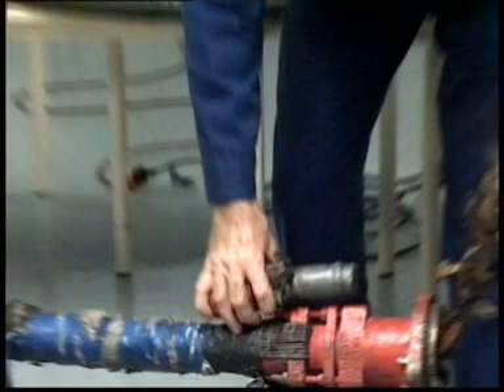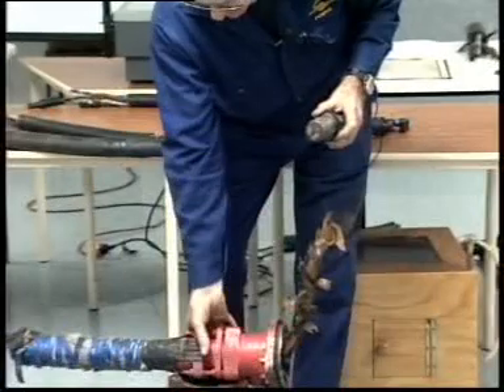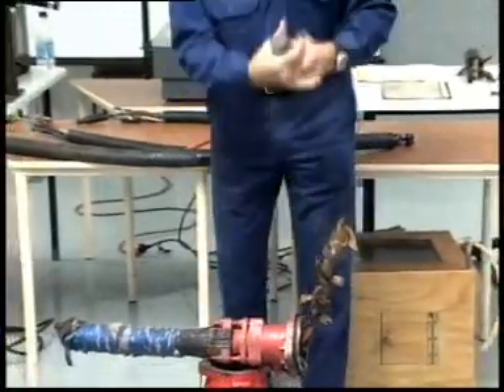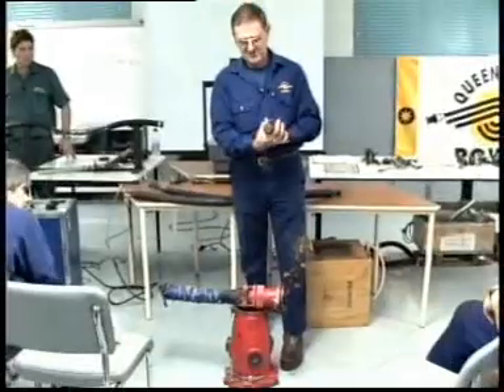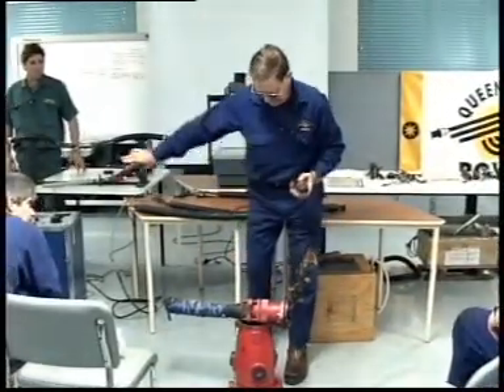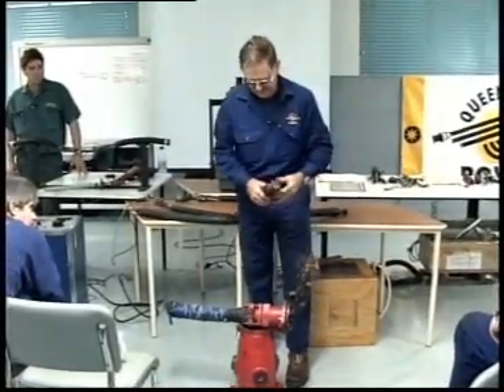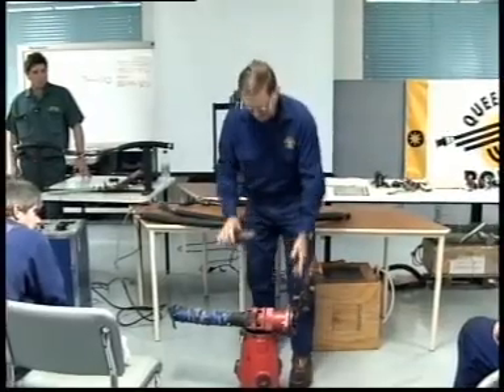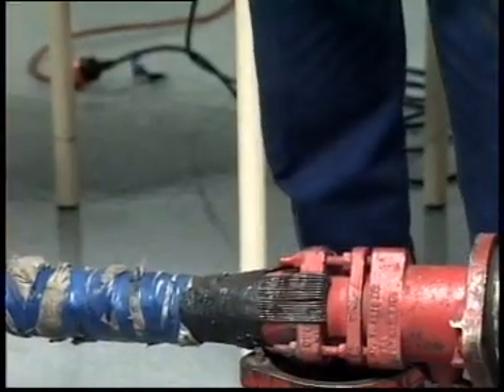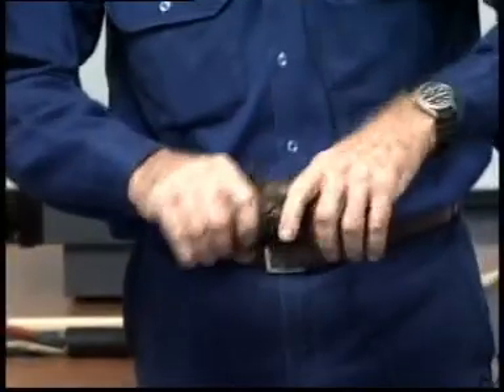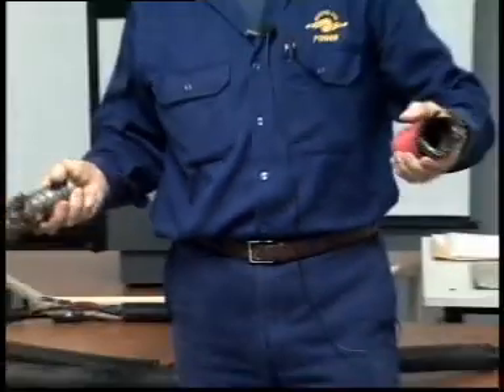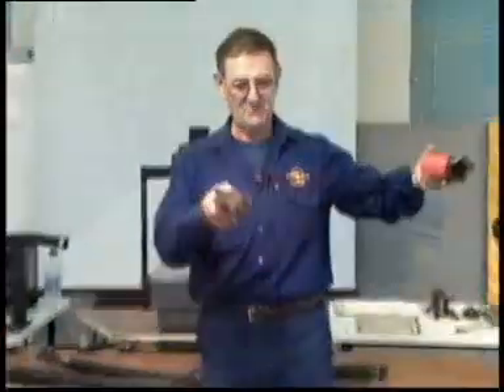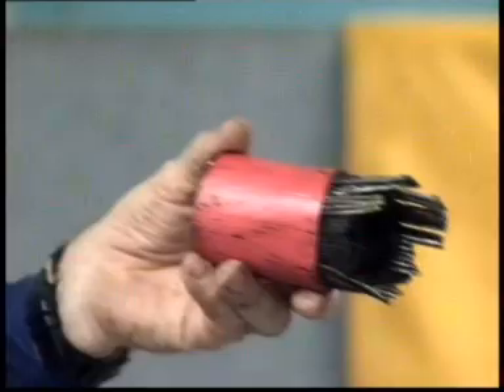This particular part sits in there, and that's why it's shaped like that, because there's a set of lead clamps that sit in the back underneath this cone here that hold it mechanically tight and also supply a good earthing medium for the full length of the cable. When we got this one in, we found that the problem was in the plug, so we chopped it off, pulled it out, and then the guy doing the repair cut it off back here, and when he did, we found that the lead was completely broken off all the way around in that section.